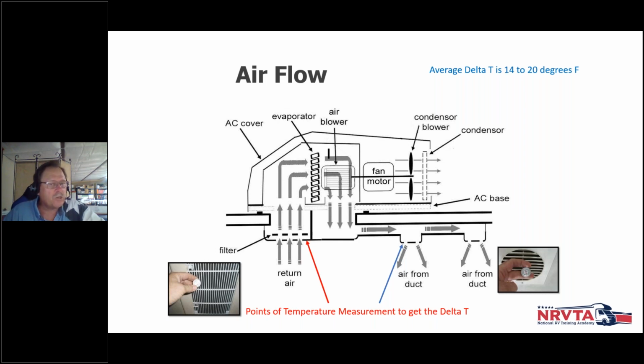Now, one of the things I need to make sure you understand is that if you have more than one air conditioner on your roof, you only want to do the delta on each air conditioner by itself. You don't want to have two or three air conditioners going, because you might have a weak one that's being covered by a strong air conditioner. What we want to know is what each one of these is capable of doing. So we should expect to see, on a good summer day, a 14 to 22 degree temperature difference.